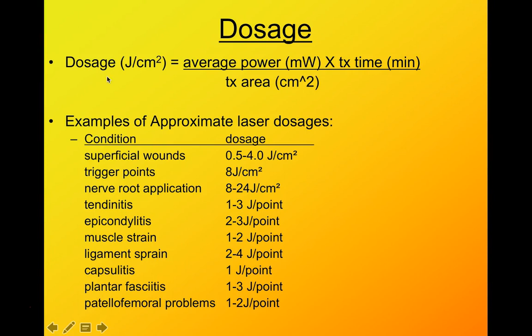Your treatment area you're going to determine, but it's potentially the size of your probe. So if you just have a single point probe, or if you have that cluster probe, and then if you're going to do multiple of those, you would have to take that into account in your treatment area. And then that's going to affect your time. So you can either usually set your time, or you can set your dosage if you have a chart, or if your machine gives you certain dosages or the research. So if you set your dosage, usually the machine will automatically set you your time based on the area that you selected, as well as your power that your machine can do. If you're not setting dosage and you set this, it will come up with your dosage for you.